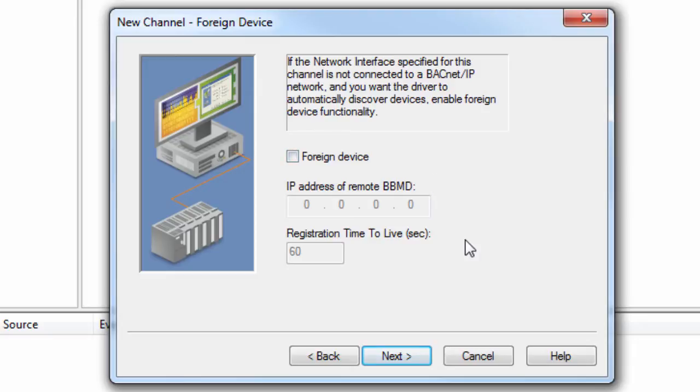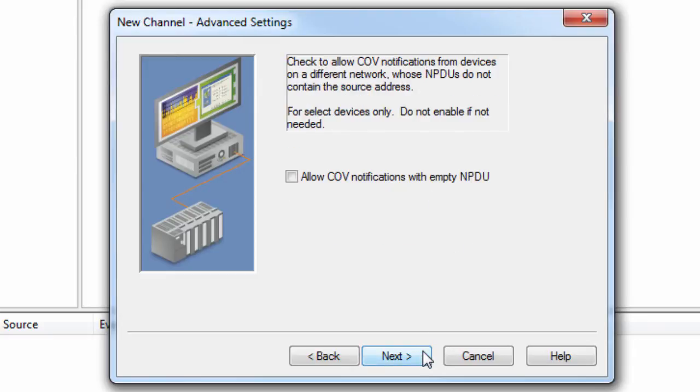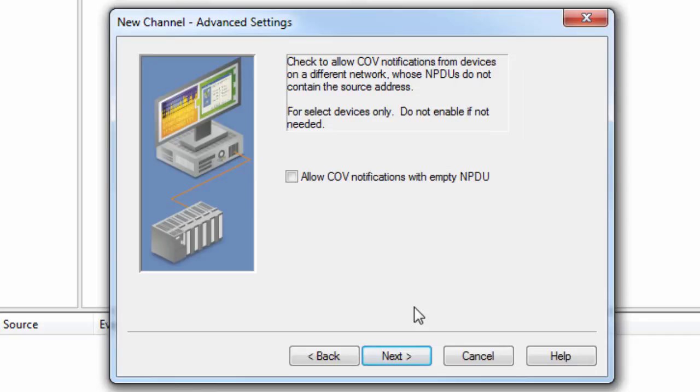Click Next to set whether or not the driver allows change of value notifications to be processed from a BACnet device on a different BACnet network whose NPDUs do not contain the source address. This setting is not commonly used and may decrease performance on BACnet networks with many COV notifications or broadcast requests.